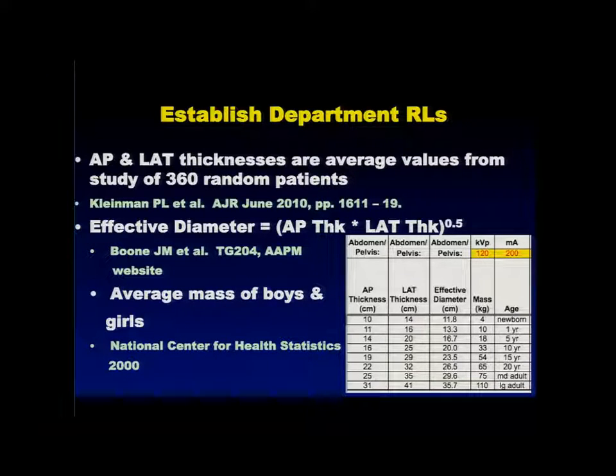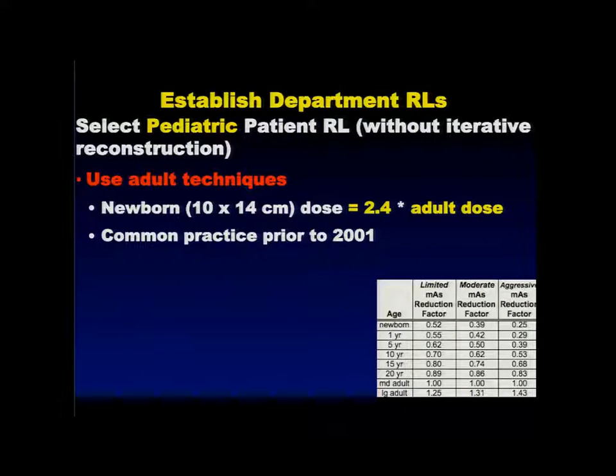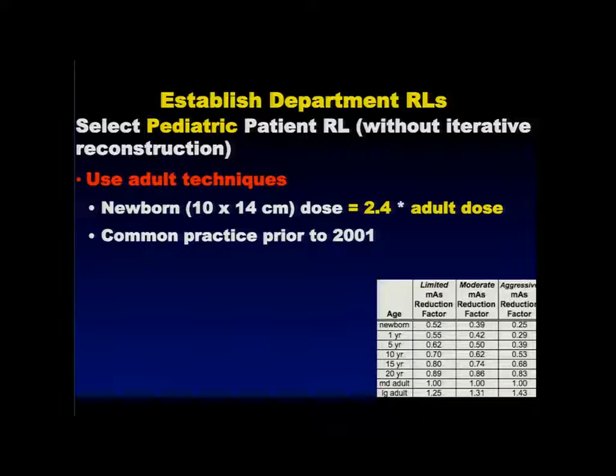The table also includes mass from a National Center for Health Statistics publication. I'm trying to give people whatever they're most comfortable working with — the lateral dimension, weight, or age. For a newborn: 10 cm AP, 14 cm lateral, effective diameter 11.8 cm, and 4 kg weight. If you don't adjust techniques for kids — which is essentially what everybody did prior to 2001 — the newborn abdominal dose is 2.6 times higher than the adult dose, reflecting the 2.6-fold difference between a 10 cm and 32 cm phantom.